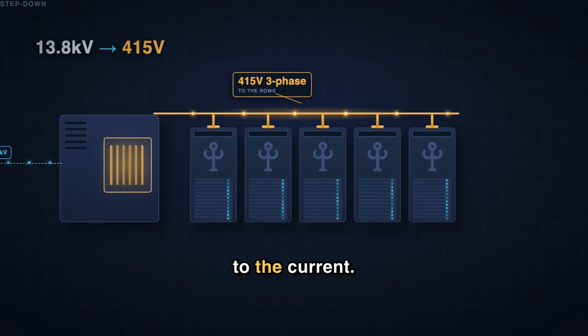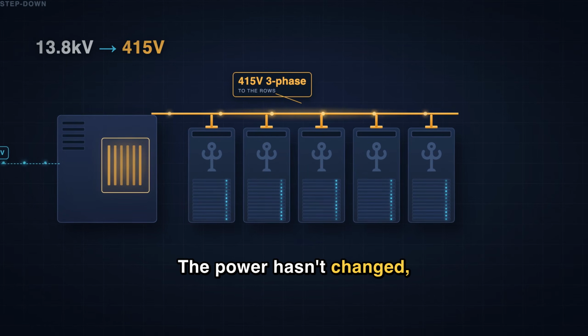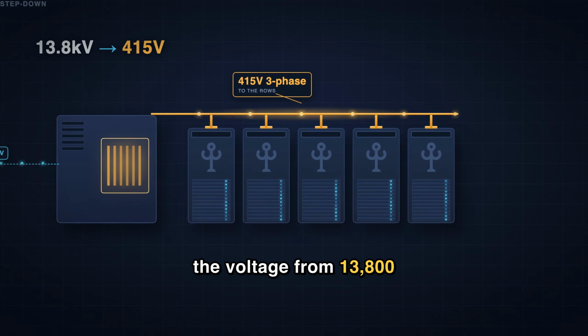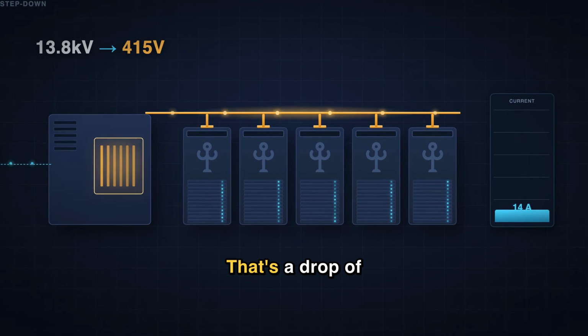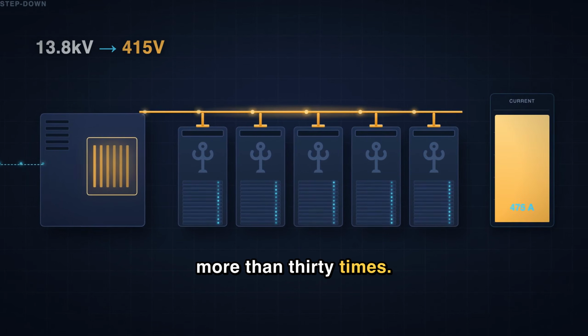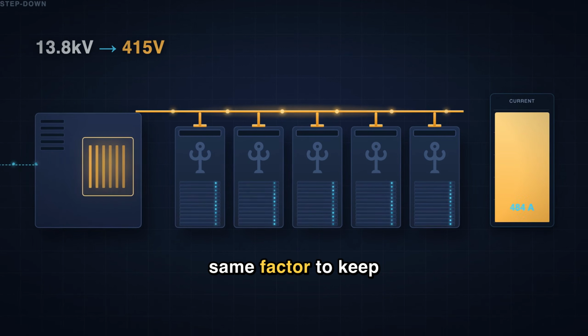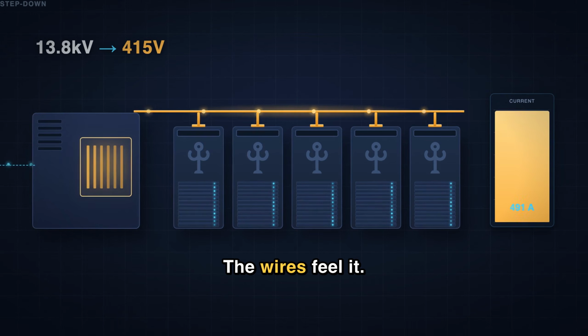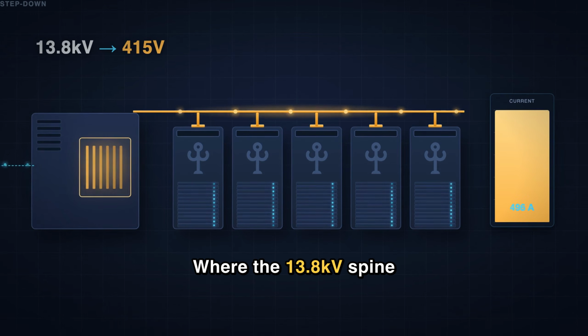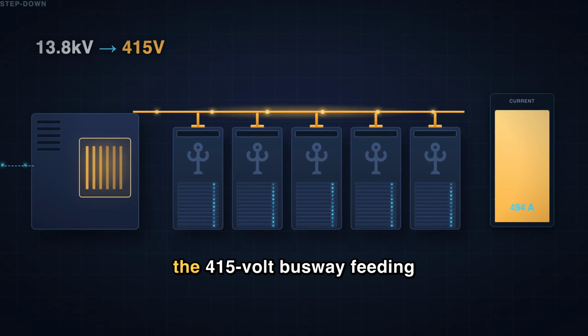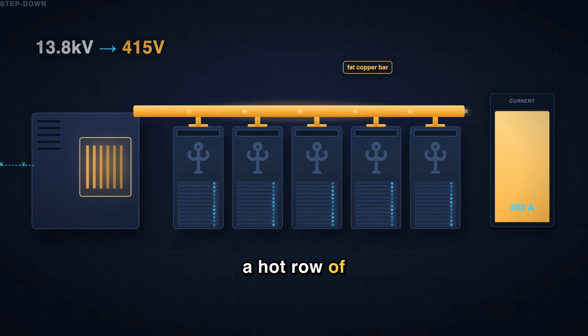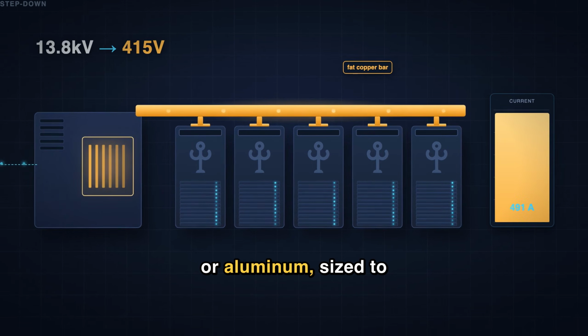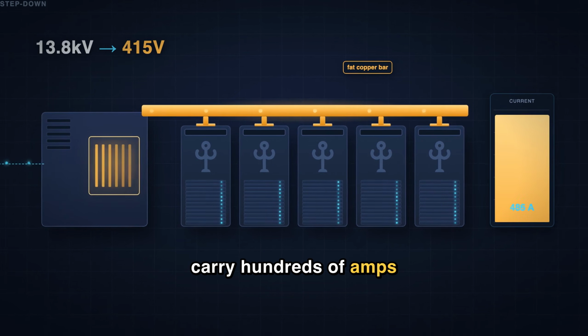But watch what happens to the current. The power hasn't changed, and we just cut the voltage from 13,800 down to 415. That's a drop of more than 30 times. So the current has to jump by that same factor to keep the power constant. The wires feel it. Where the 13.8 kilovolt spine was a slim run, the 415 volt busway feeding a hot row of AI racks is a fat bar of copper or aluminum, sized to carry hundreds of amps without overheating.